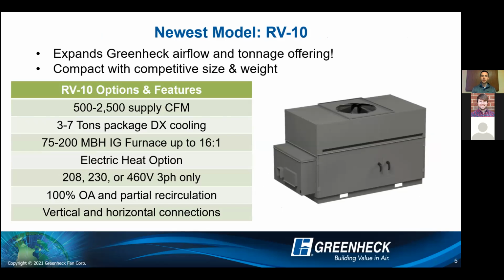So that one is specifically 3 to 7 tons, up to 200 MBH of gas heat, has an electric heat option, and it does have the 208, 230, or 460 volt options as well. So can be 100% outside air, or as I mentioned, can have partial recirc. That 20 to 100% outdoor air is generally where you want to live with this type of equipment. Also did design that housing with vertical and horizontal connections to make it easier for installation purposes.